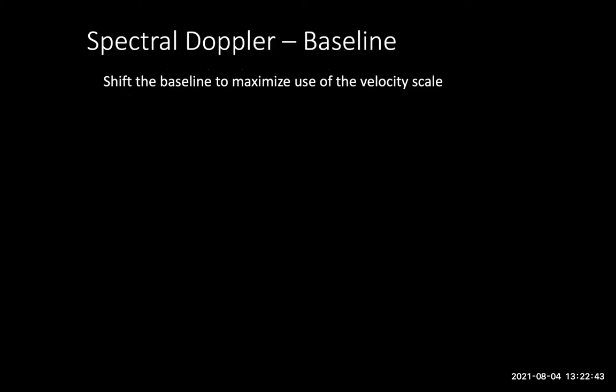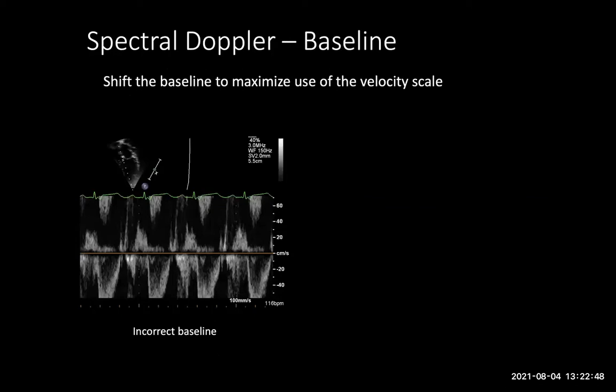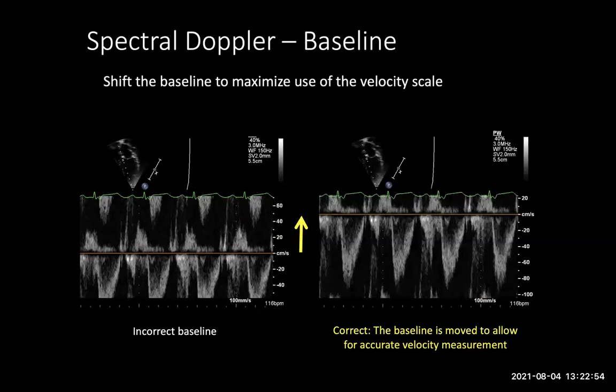We can also shift the baseline to allow for maximum use of the tracing. The baseline here has not been changed, and we can see that the flow is wrapping around. So we can shift the baseline up, and now we can see the entire flow pattern and again be able to measure it correctly.